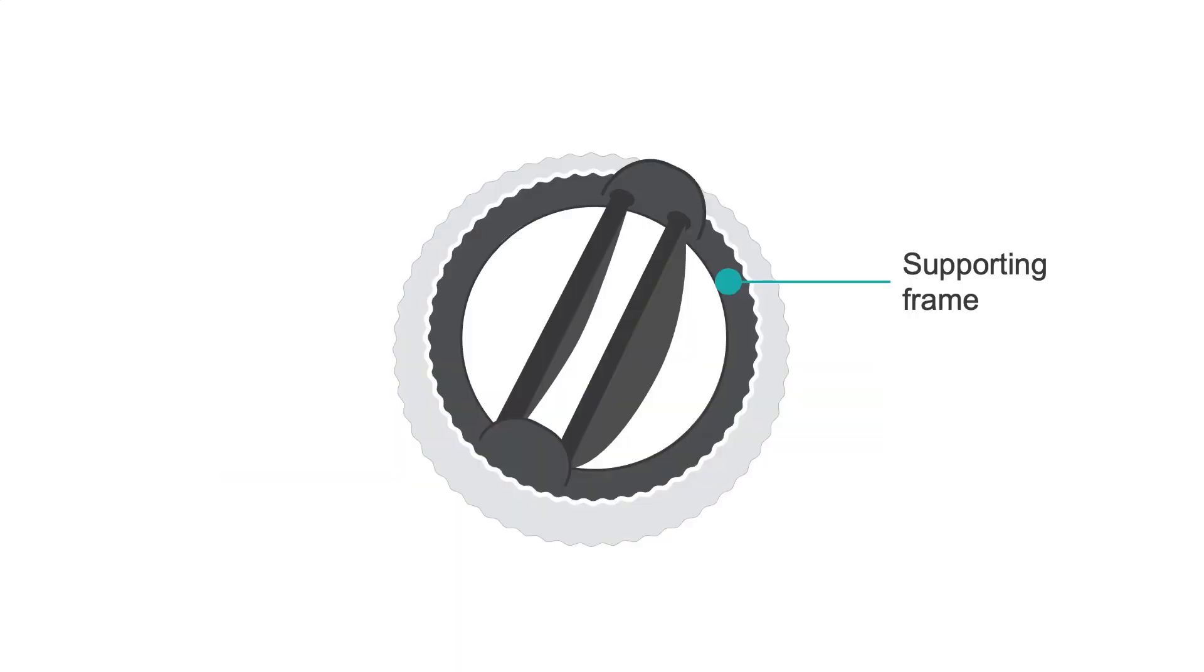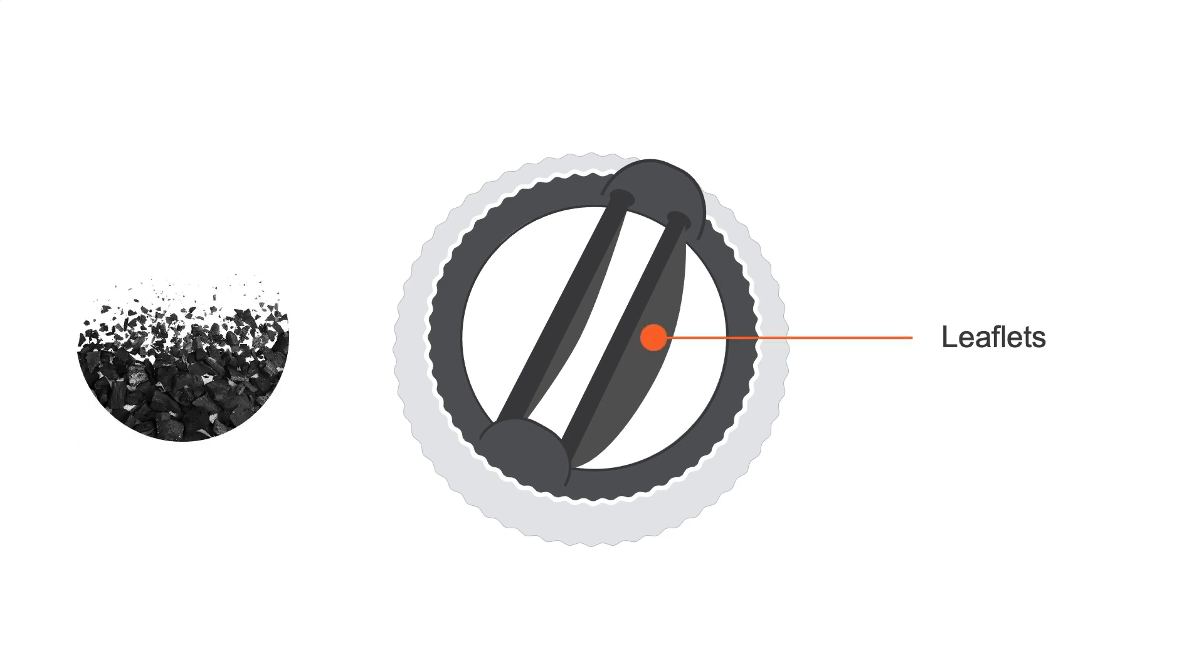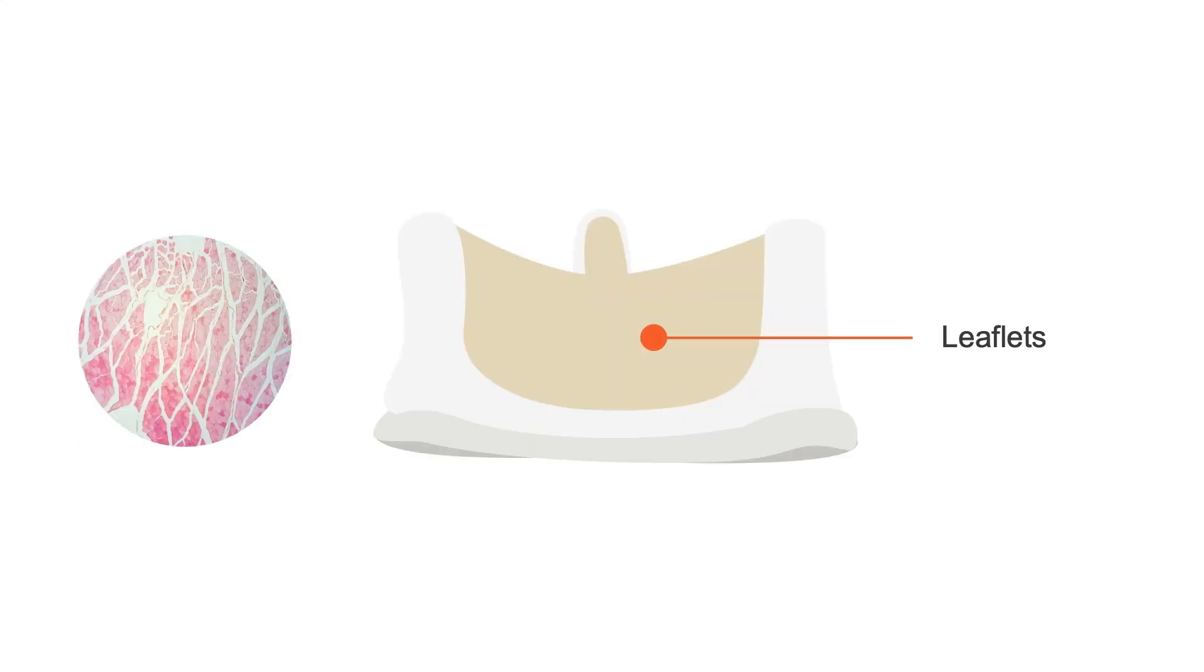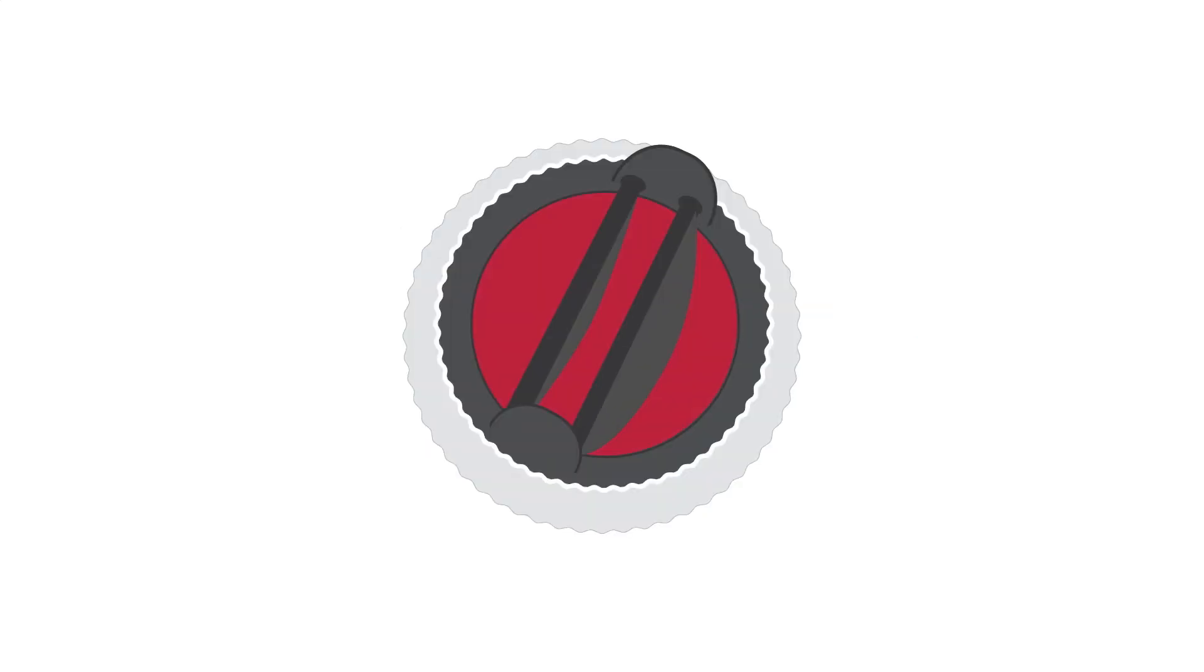The supporting frame is composed of alloy or polymer materials that absorb some of the forces acting on the leaflets. The leaflets are made of carbon for mechanical valves and tissue for bioprosthetic valves, and they can open and close to allow blood flow across the chambers.